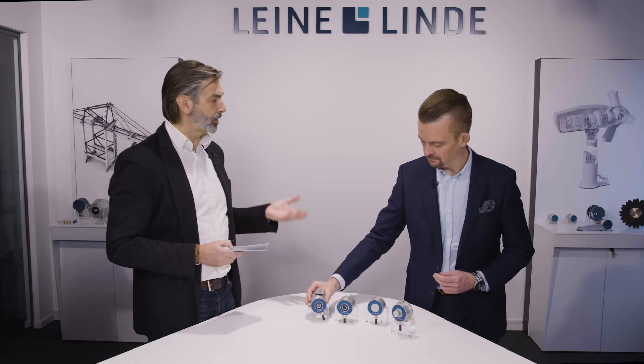Let's talk about extending the lifetime of these products — what's in them that's not in traditional products? Leine Linde is recognized for having durable encoders that can cope with really harsh environments. When defining the lifetime of an encoder, it depends on parameters like ambient conditions, how well it is installed, and the bearings — one of the key lifetime-limiting factors. In conventional 58 millimeter encoders, the bearing size was sometimes limited by the technology. As we now go inductive with the M500 series, we have been able to remove lenses and optical components that took space, and therefore we can use much bigger bearings today compared with prior models.